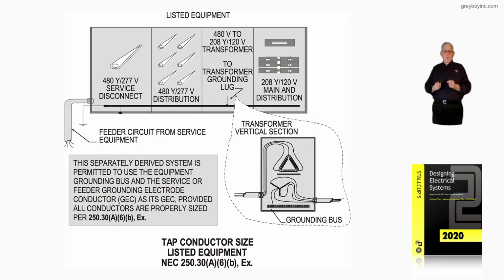But here we just have one. And see, that would give a different potential. You're connecting to the structural steel, and then that grounded bar that you see there is connected into your electrode system, 250.50, and you would most likely have different impedances there.